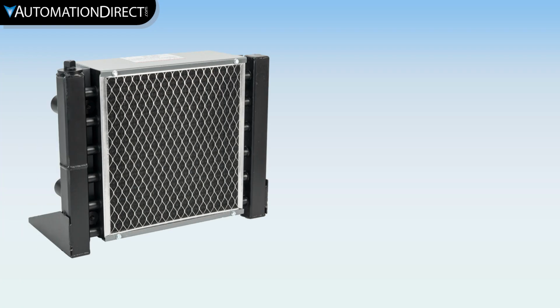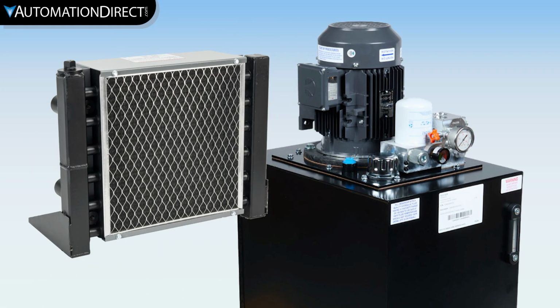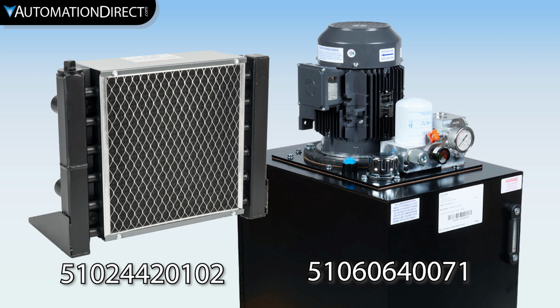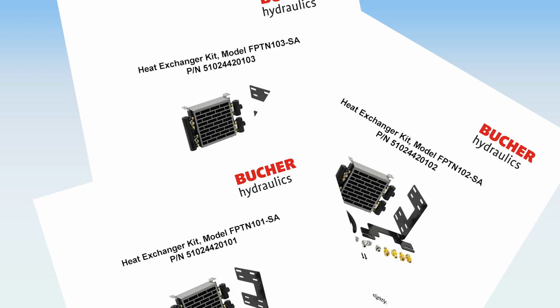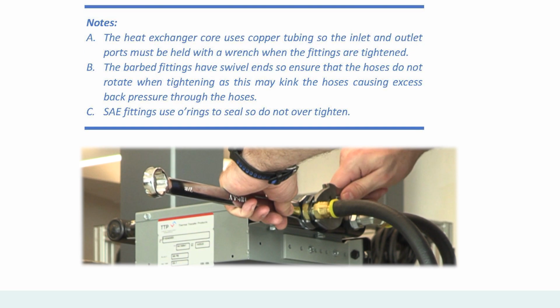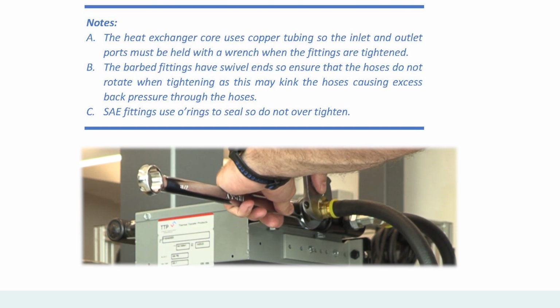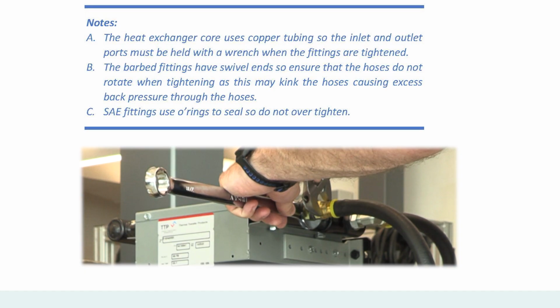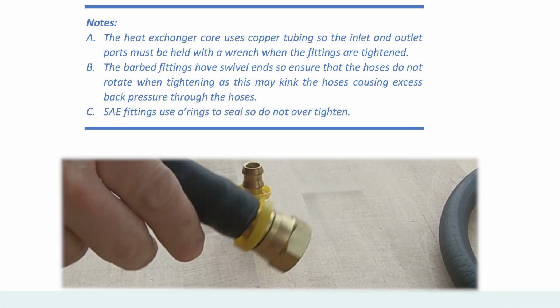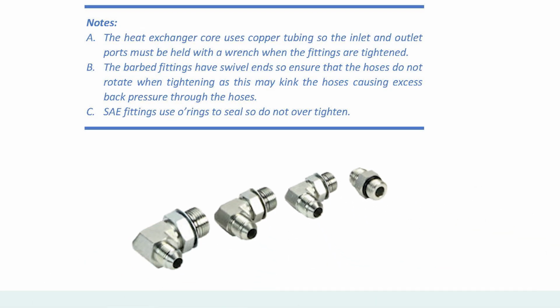A few notes before we get started. This installation is specific for the power unit and the heat exchanger we are using, so be sure to check the instructions that came with your heat exchanger because the installation varies a bit between models. The heat exchanger core uses copper tubing, so the inlet and outlet ports must be held with a wrench when these fittings are tightened. The barb fittings have swivel ends, so ensure the hoses do not rotate when tightening, as this may kink the hoses, causing excessive back pressure. SAE fittings use O-rings to seal, so do not over-tighten.